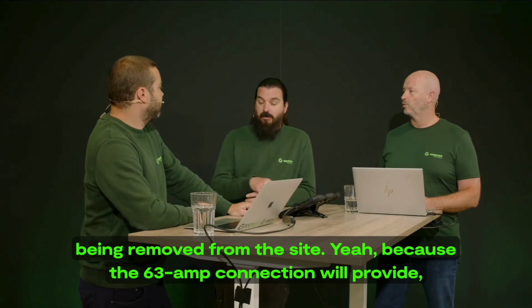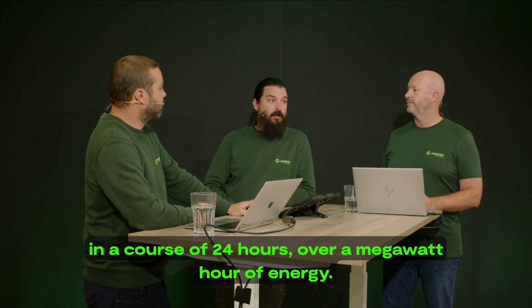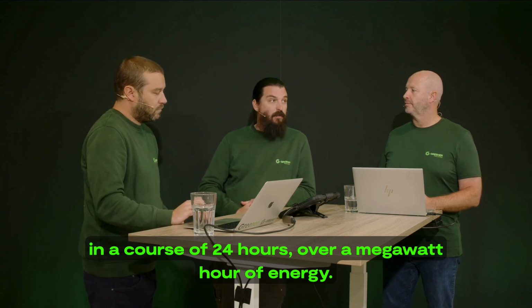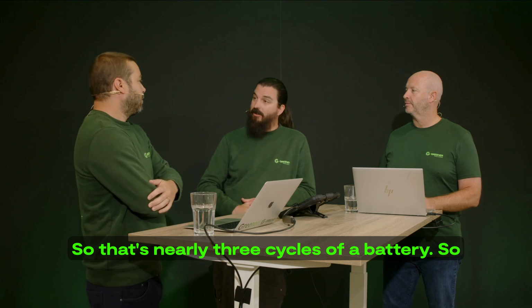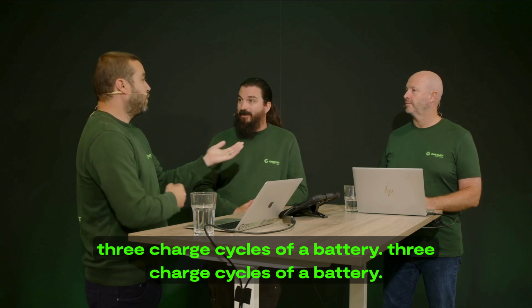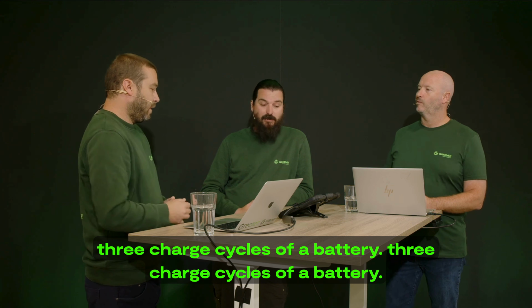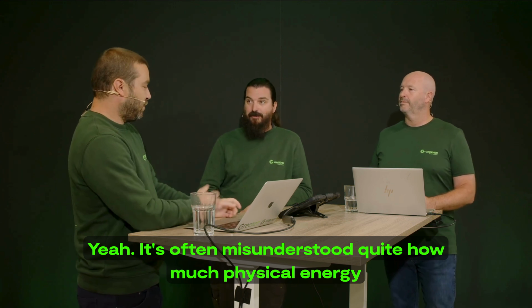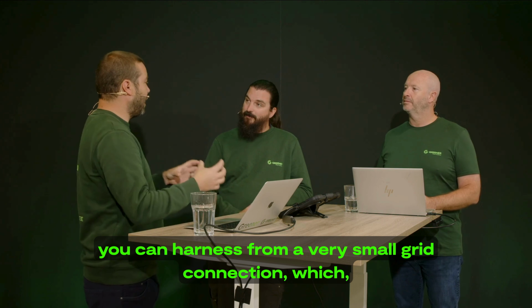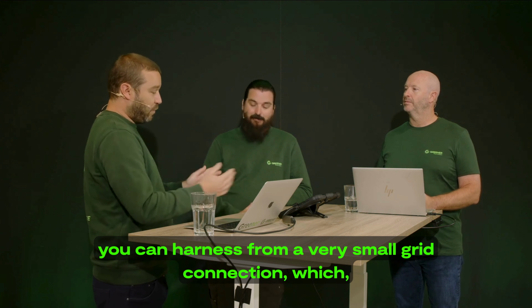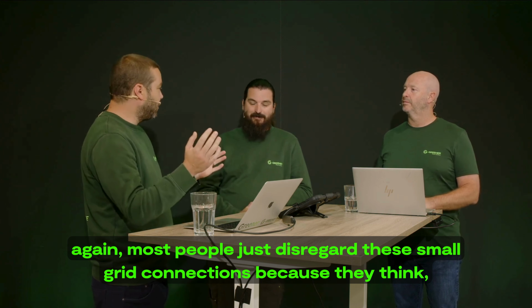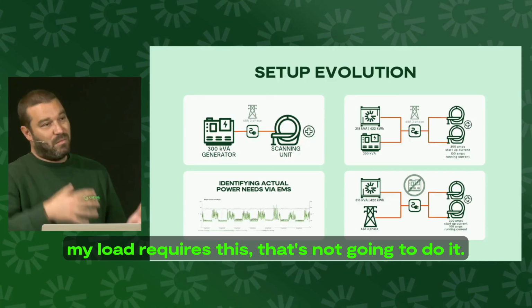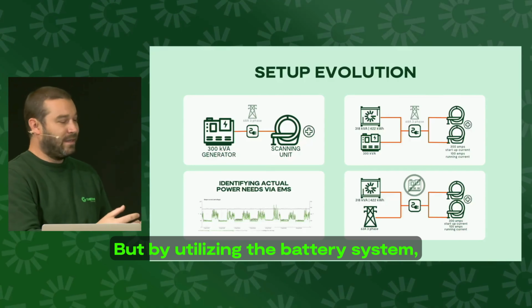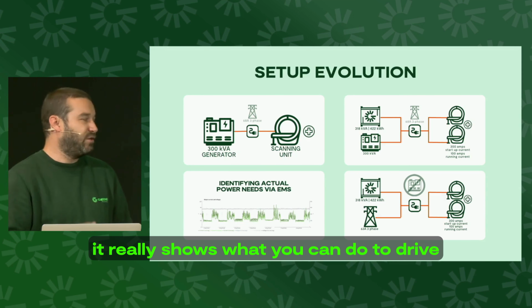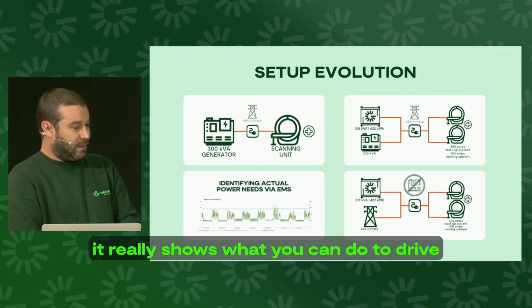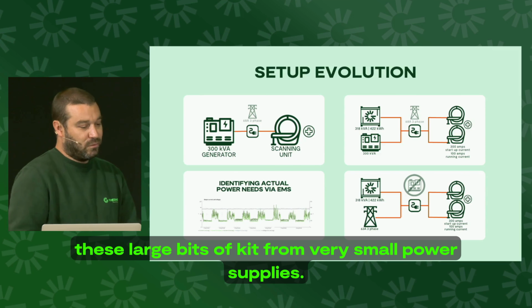Because the 63 amp connection will provide, in the course of 24 hours, over a megawatt hour of energy. So that's nearly 3 charge cycles of a battery, just out of the wall. It's often misunderstood quite how much physical energy you can harness from a very small grid connection, which again, most people just disregard because they think my load requires this, that's not going to do it. But by utilising the battery system, it really shows what you can do to drive these large bits of kit from very small power supplies.